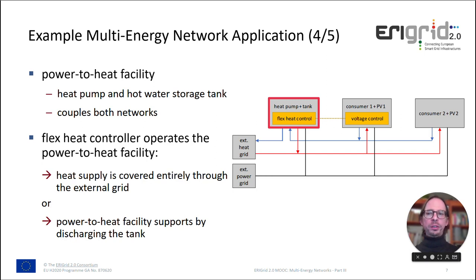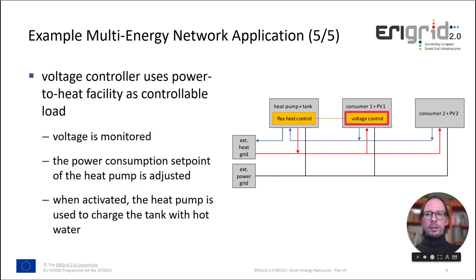To operate this facility, we use the so-called flex-heat controller. This controller determines whether the heat supply is covered entirely through the external grid, or if the power-to-heat facility supports by discharging the tank. In addition, there is a voltage controller that uses the power-to-heat facility as a controllable load. It monitors the voltage at consumer 1 and adjusts the power consumption setpoint for the heat pump. Whenever the heat pump is activated, it is used to charge the tank with hot water.